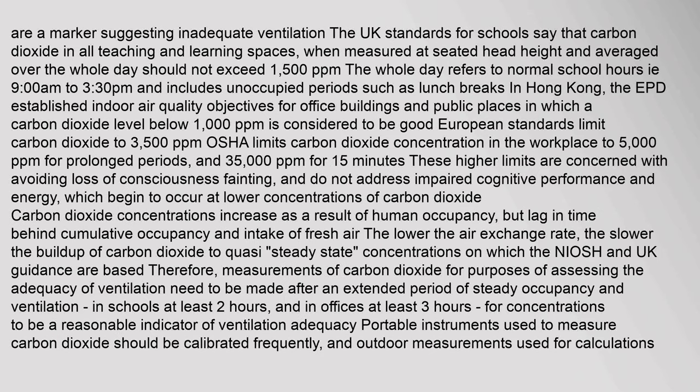To eliminate most complaints, the total indoor CO₂ level should be reduced to a difference of less than 600 ppm above outdoor levels. The National Institute for Occupational Safety and Health (NIOSH) considers that indoor air concentrations of carbon dioxide exceeding 1000 ppm are a marker suggesting inadequate ventilation. The UK standards for schools say that carbon dioxide in all teaching and learning spaces, measured at seated head height and averaged over the whole day, should not exceed 1500 ppm.